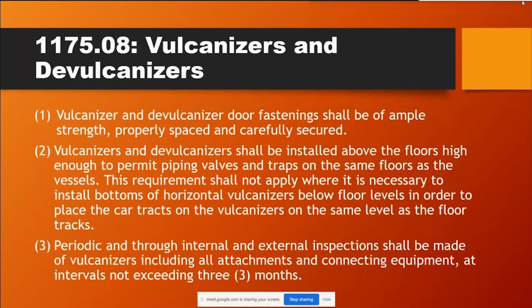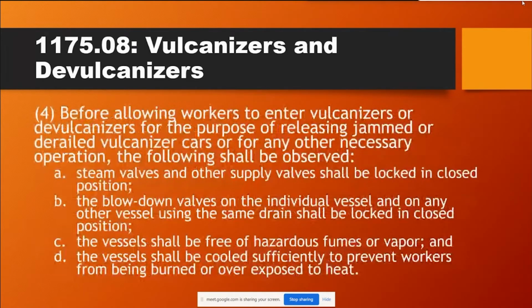Periodic and thorough internal and external inspections shall be made of vulcanizers, including all attachments and connecting equipment, at intervals not exceeding 3 months. Before allowing workers to enter vulcanizers or devulcanizers for the purpose of releasing jammed or derailed vulcanizer cars or for any other necessary operation, the following shall be observed. Steam valves and other supply valves shall be locked in closed position. The blow-down valves on the individual vessel and on any other vessel using the same drain shall be locked in closed position. The vessel shall be free of hazardous fumes or vapor, and the vessel shall be cooled sufficiently to prevent workers from being burned or overexposed to heat.